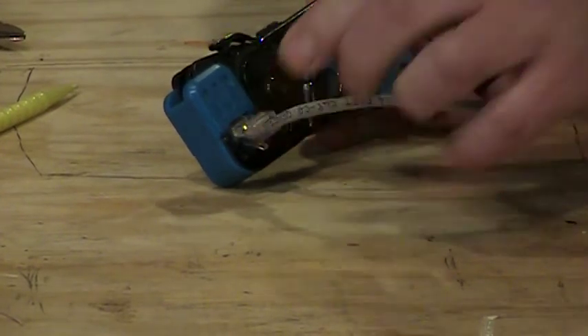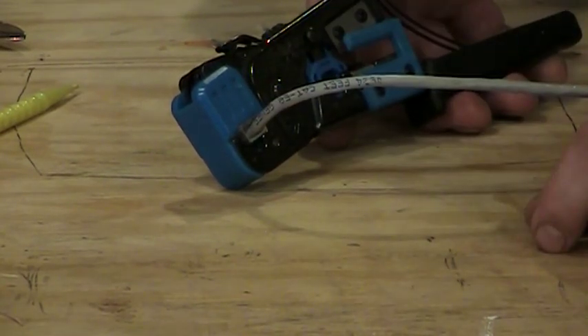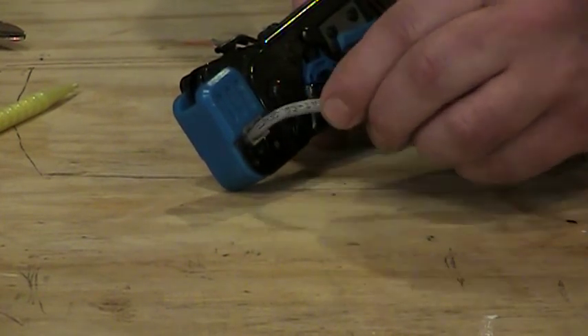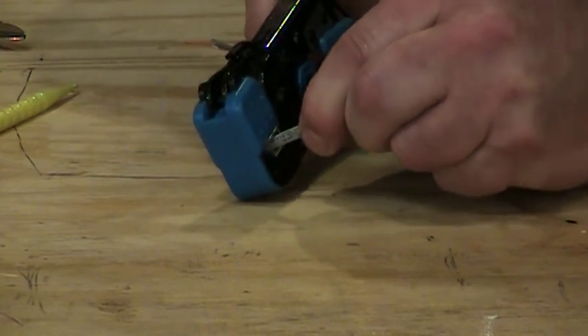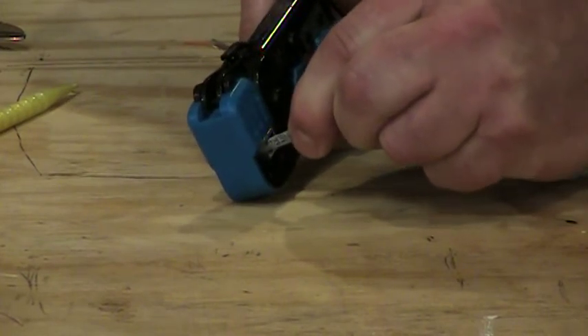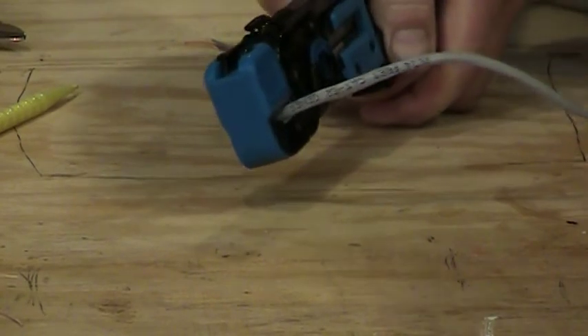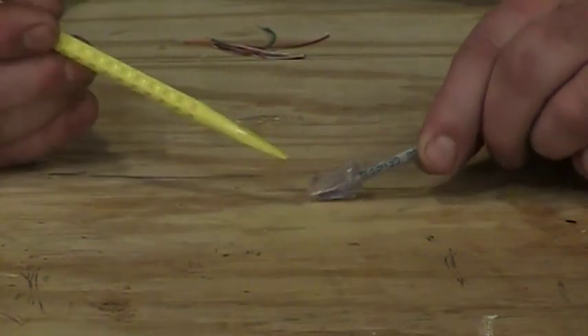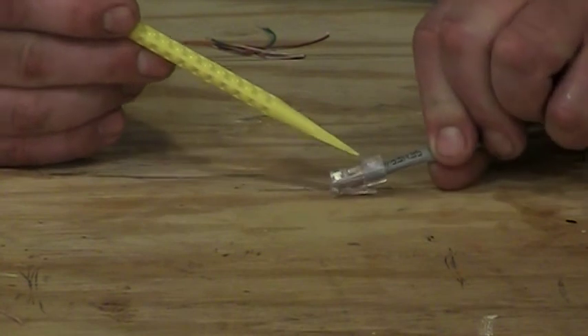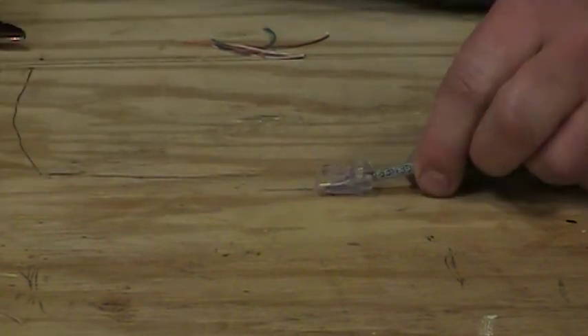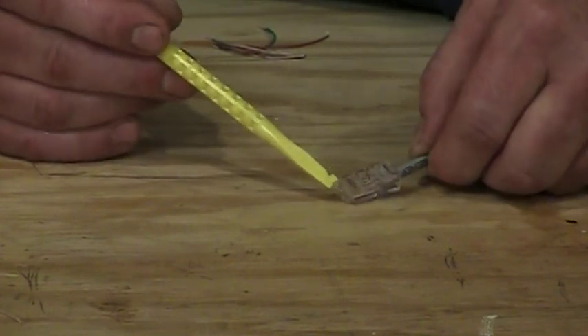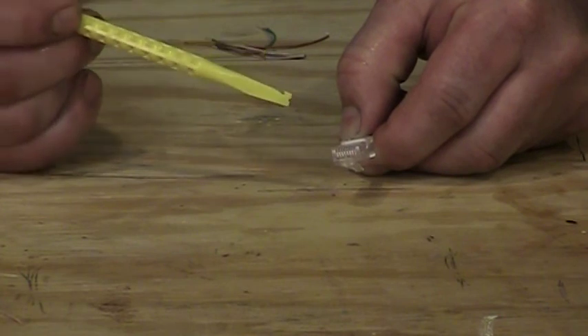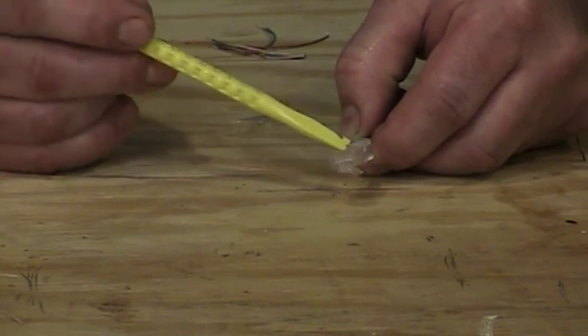We're going to crimp that inside the tool here and the connector will load right in the front die of the tool just like that. The connector will only go in one side of the tool so that you know you got in the right place. And when we go to crimp this, we don't want to be pulling the cable to one side or the other. We want to be straight up and down on it and if anything, I'm going to push this cable into the connector or into the tool so I know it's in there and bottom them out. And then I'm going to simply squeeze this down. When you squeeze this down, it drives the pins down and makes a connection for us. And when we get done with the finished product here, I can see that my gray jacket is underneath the strain relief like I like it to be. I've got my conductors all the way through the ends of the wire. The gold pins are all down like they're supposed to. And I can see all the conductors through the clear front and it looks like it's good.